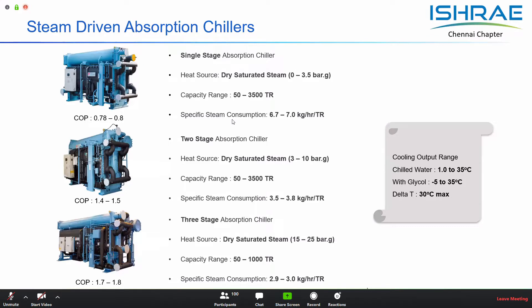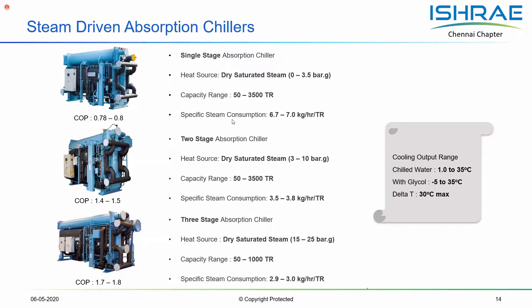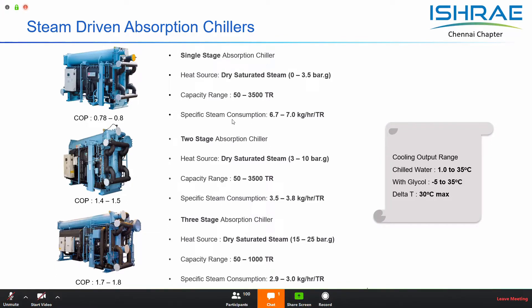The two-stage absorption unit requires higher steam pressure — around 6 to 8 bar. Because a higher grade of energy is used, this unit gives a lower steam consumption — literally half that of a single-stage chiller — and the COP of this unit is double that of the single-stage. The type of technology used is dependent on the energy source available, i.e., its temperature and pressure.